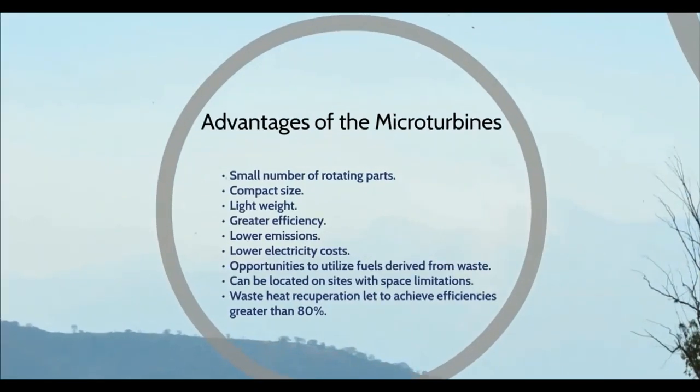Microturbines offer a number of potential advantages compared to other technologies for small-scale power generation. These include a small number of moving parts, compact size, light weight, greater efficiency, lower greenhouse gas emissions, lower electricity costs, and opportunities to utilize fuels derived from waste. They have the potential to be located on sites with space limitations for the production of power. Waste heat recovery can be used with these systems to achieve efficiencies greater than 80%.